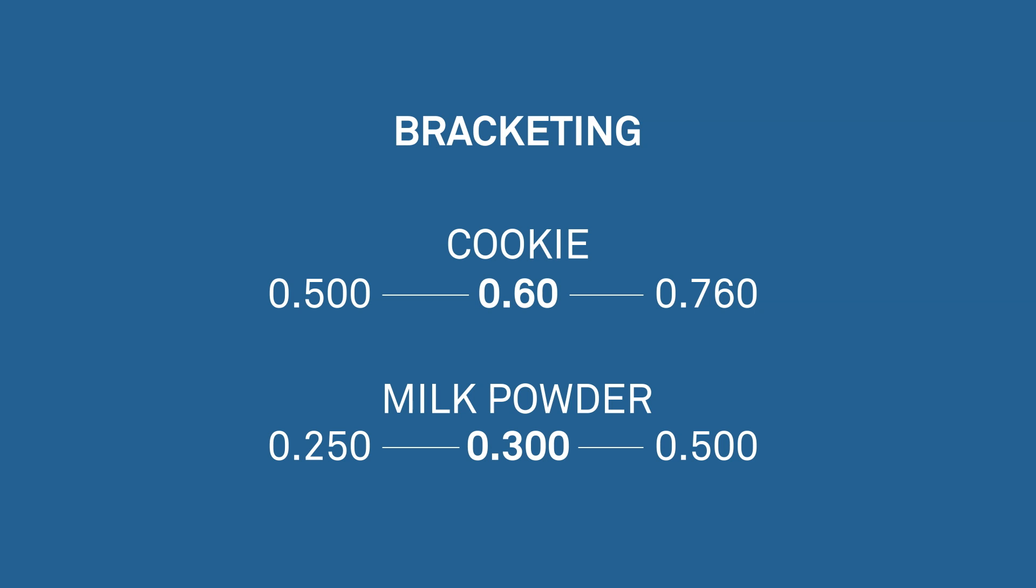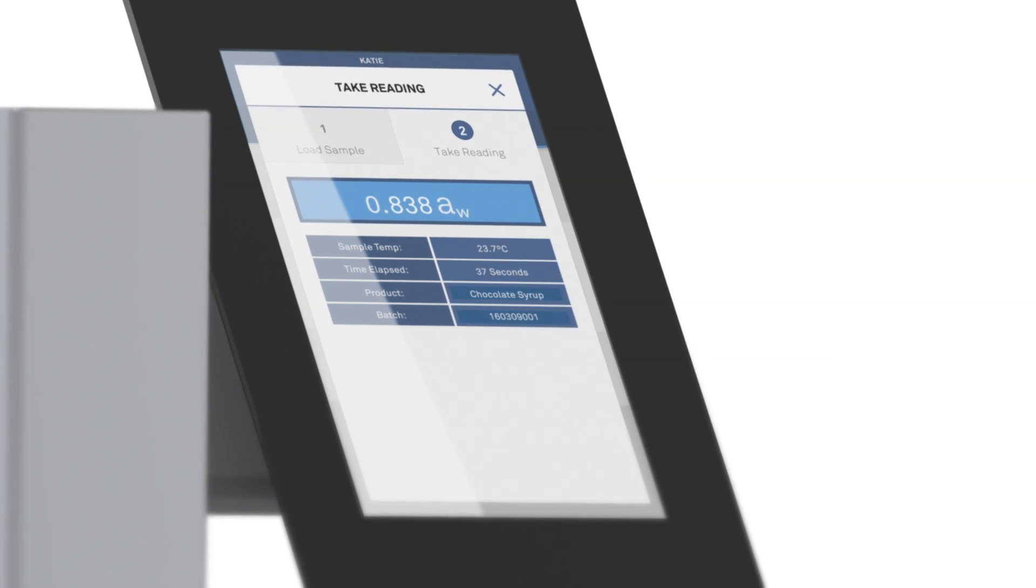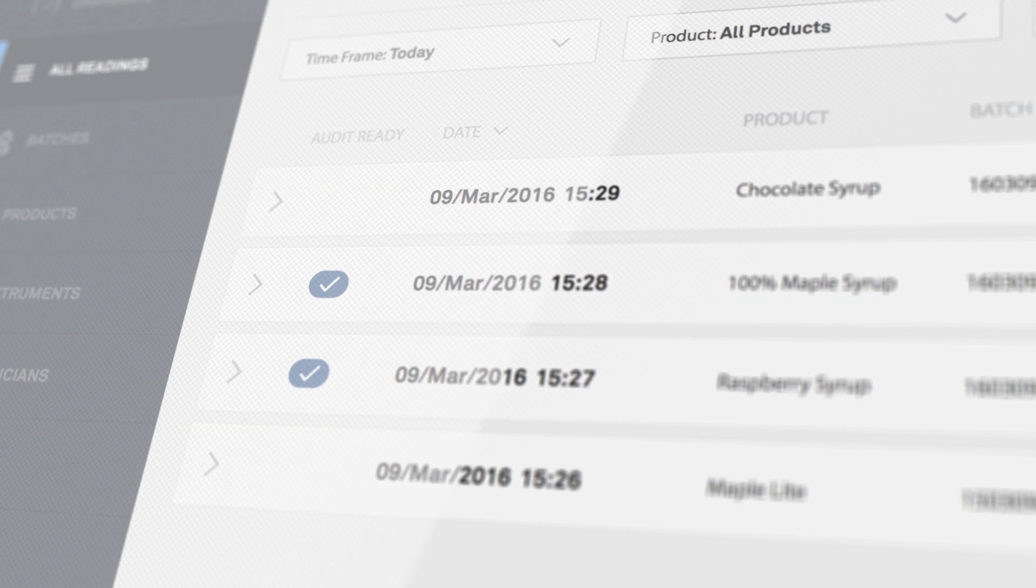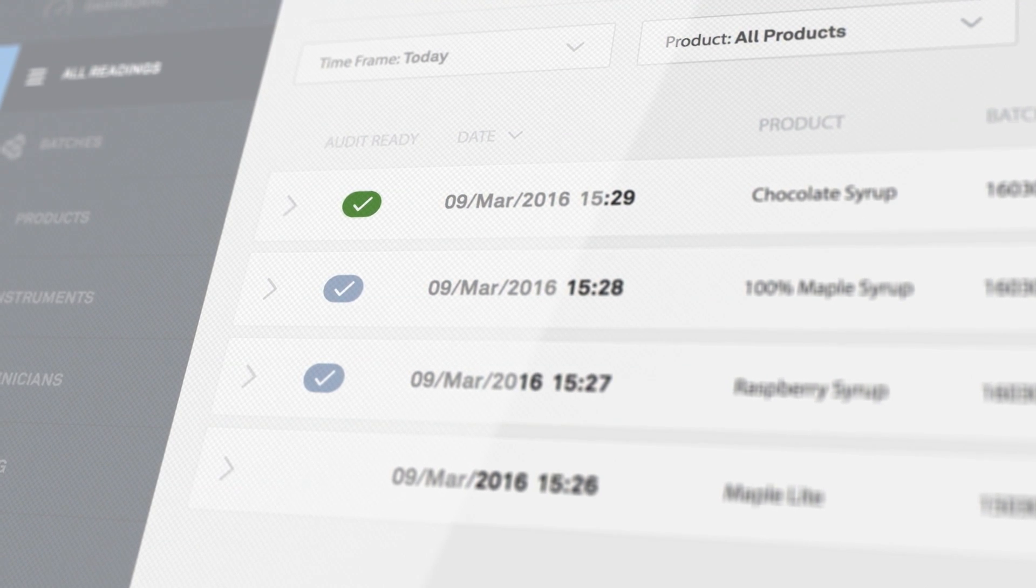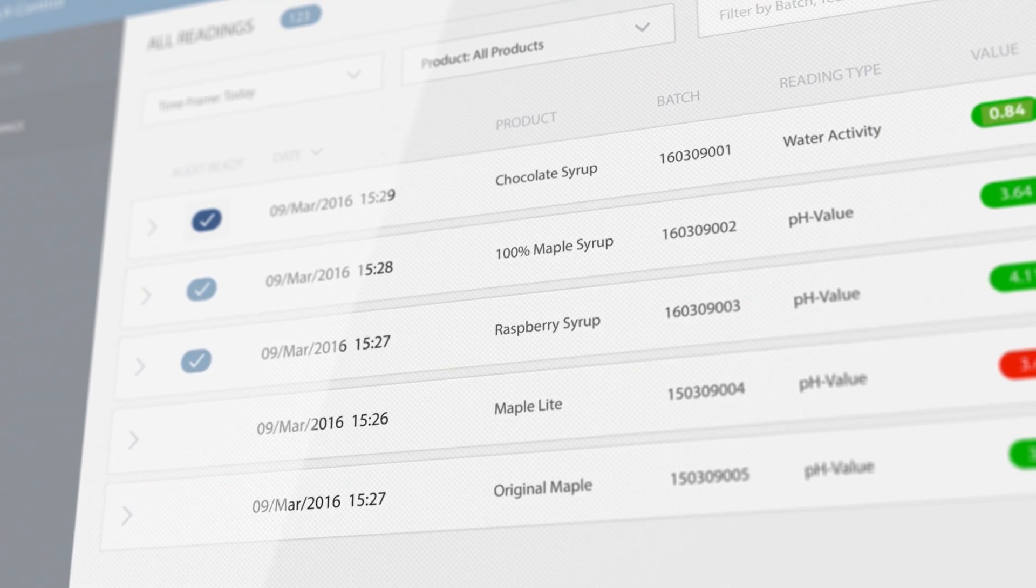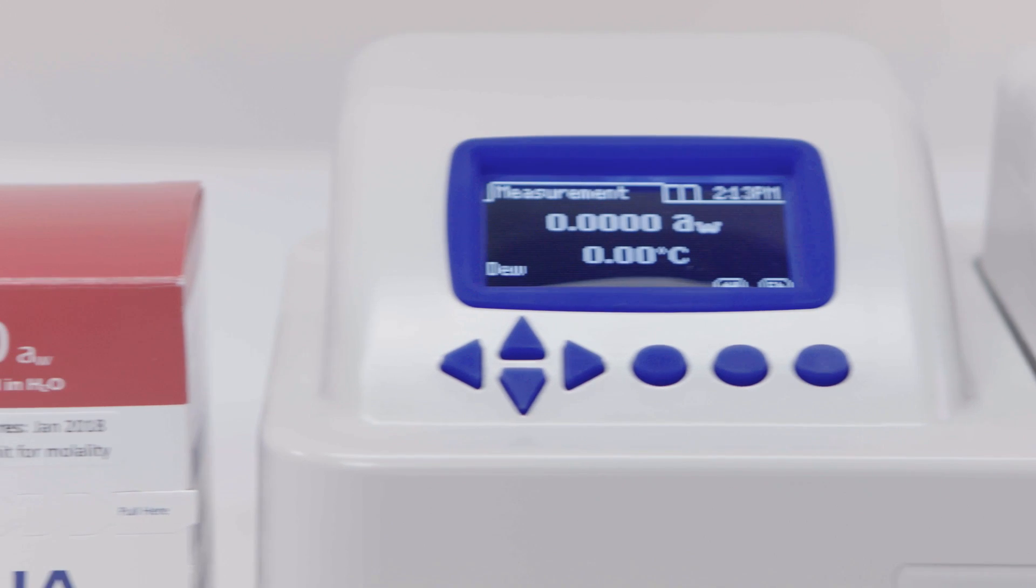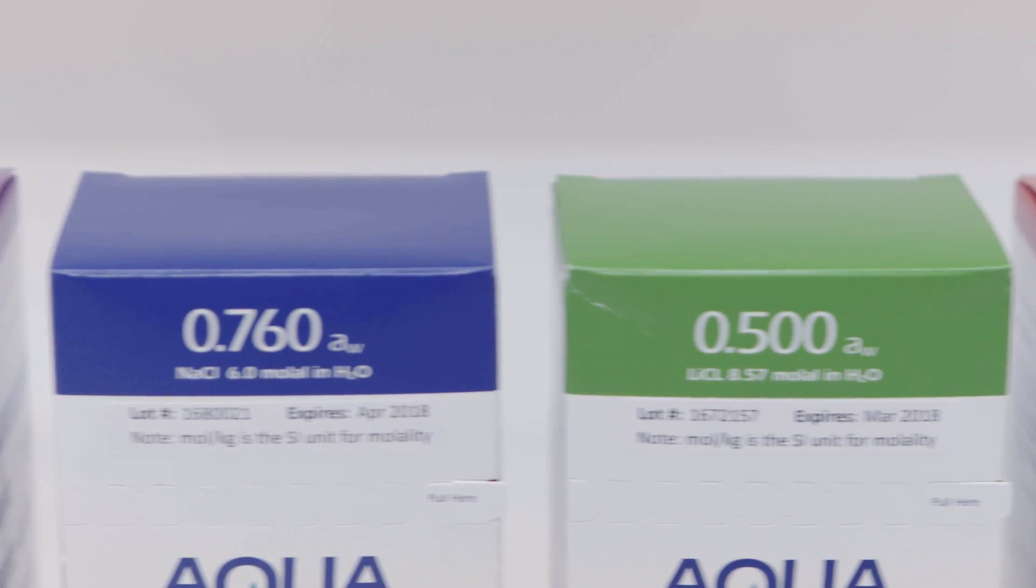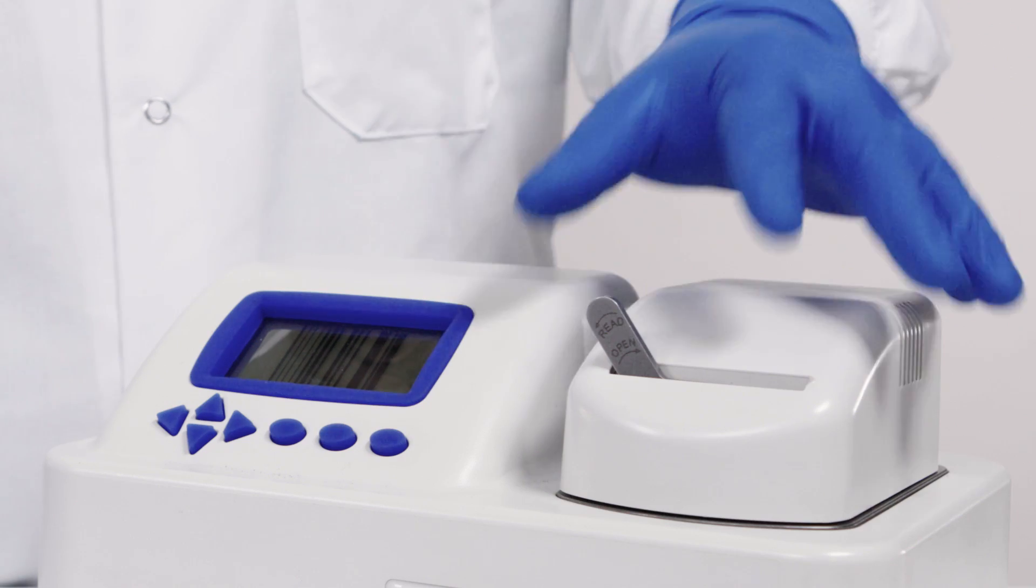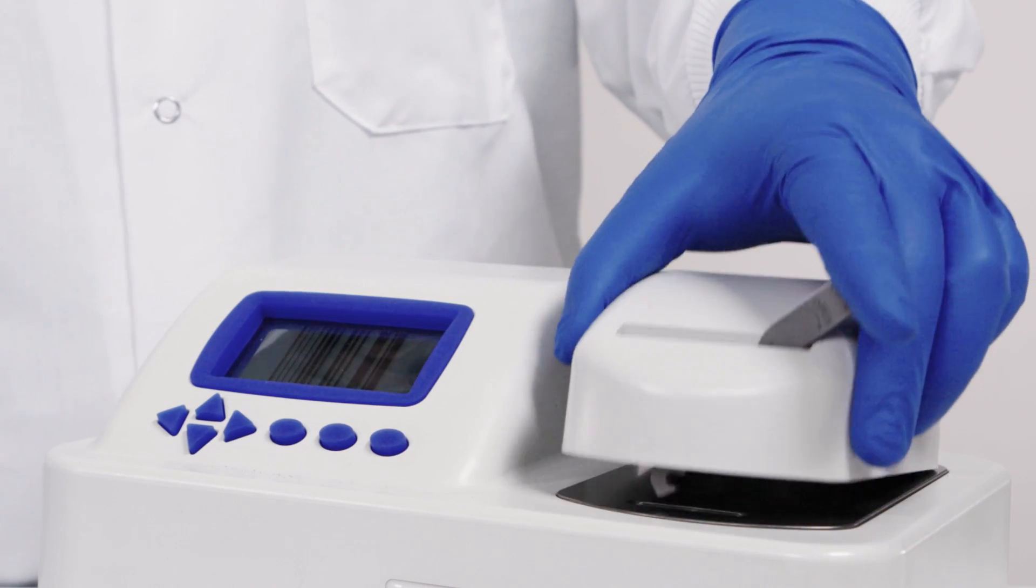We are running our verification in Scala, so the verification record can be attached to all the measurements we take this shift, but you can also record the details of your verification manually. Any reading within 0.003 of your solution's water activity is fine, as long as you're using the chilled mirror sensor. If you're checking the volatile sensor, any reading within 0.01 of your standard is fine.